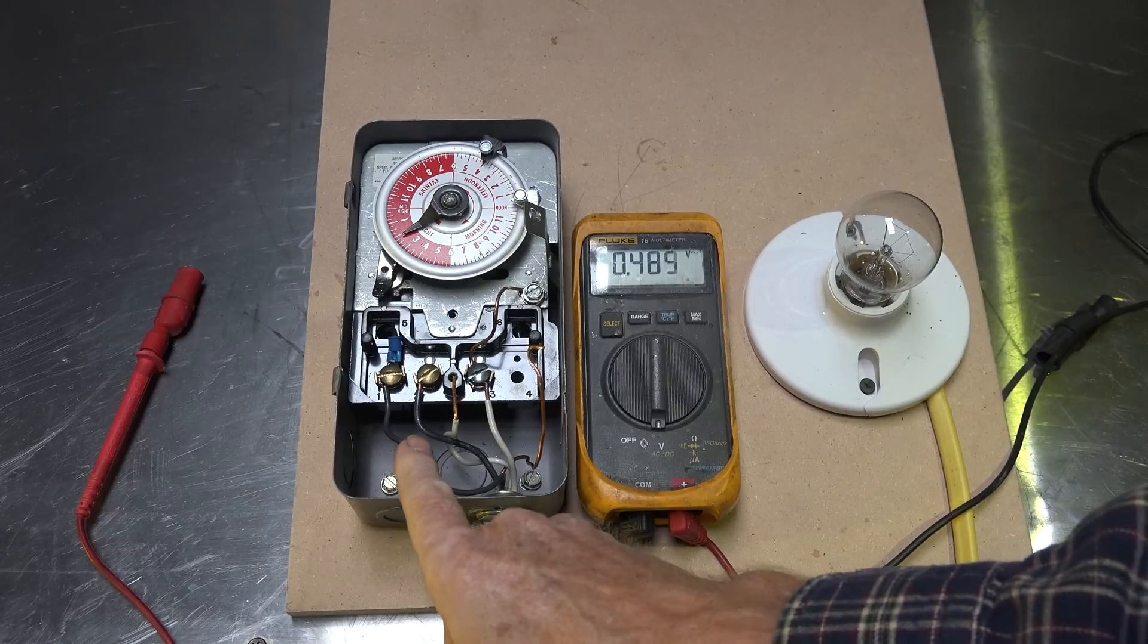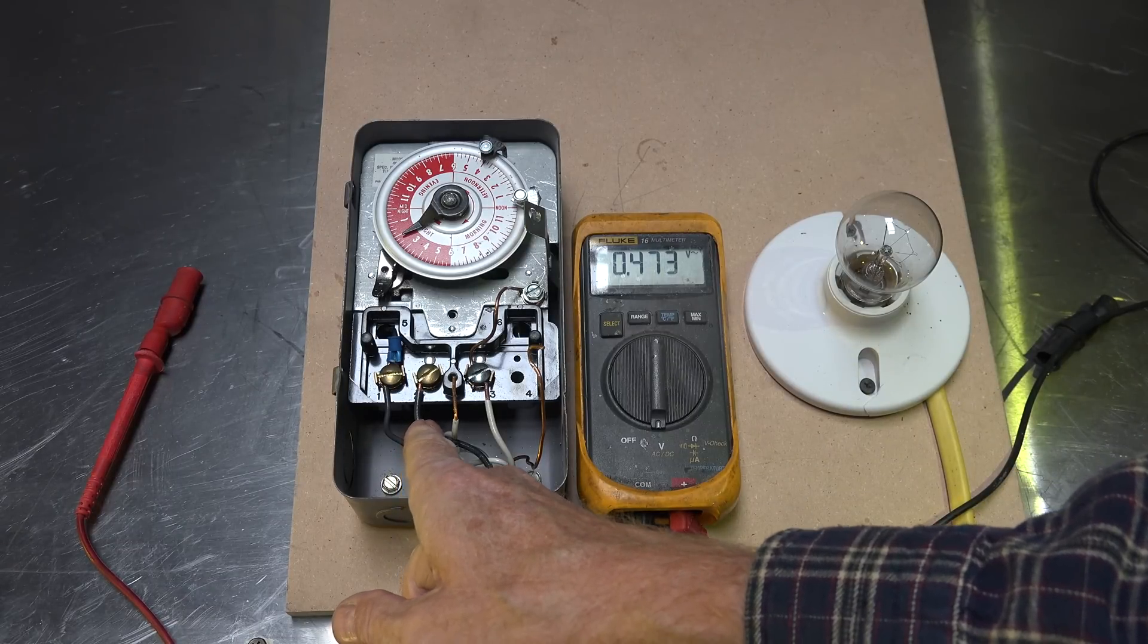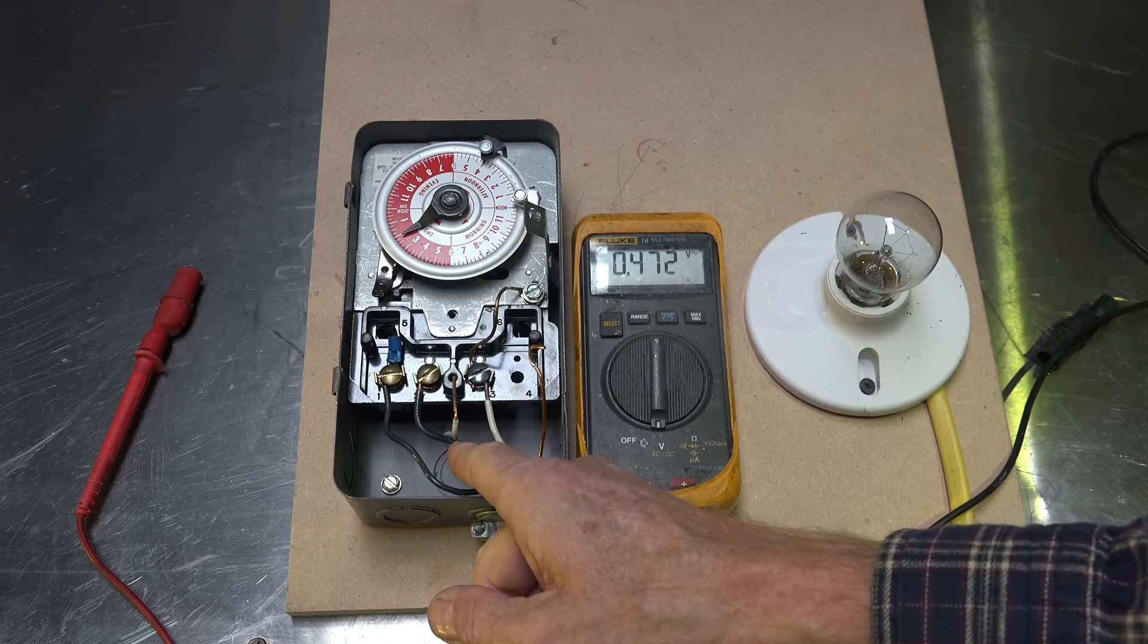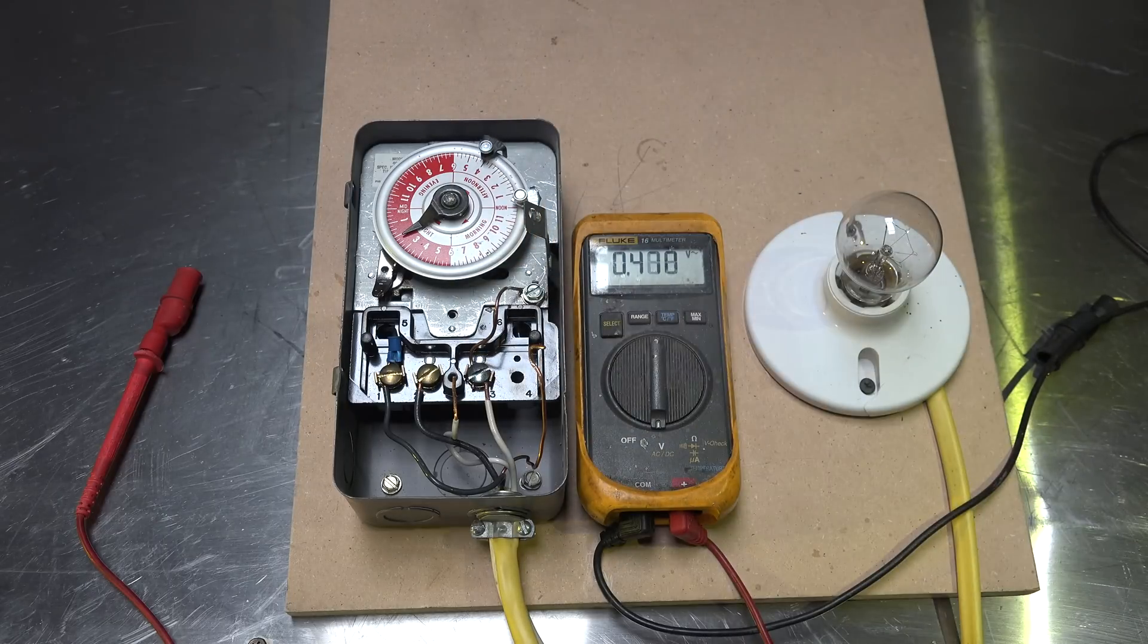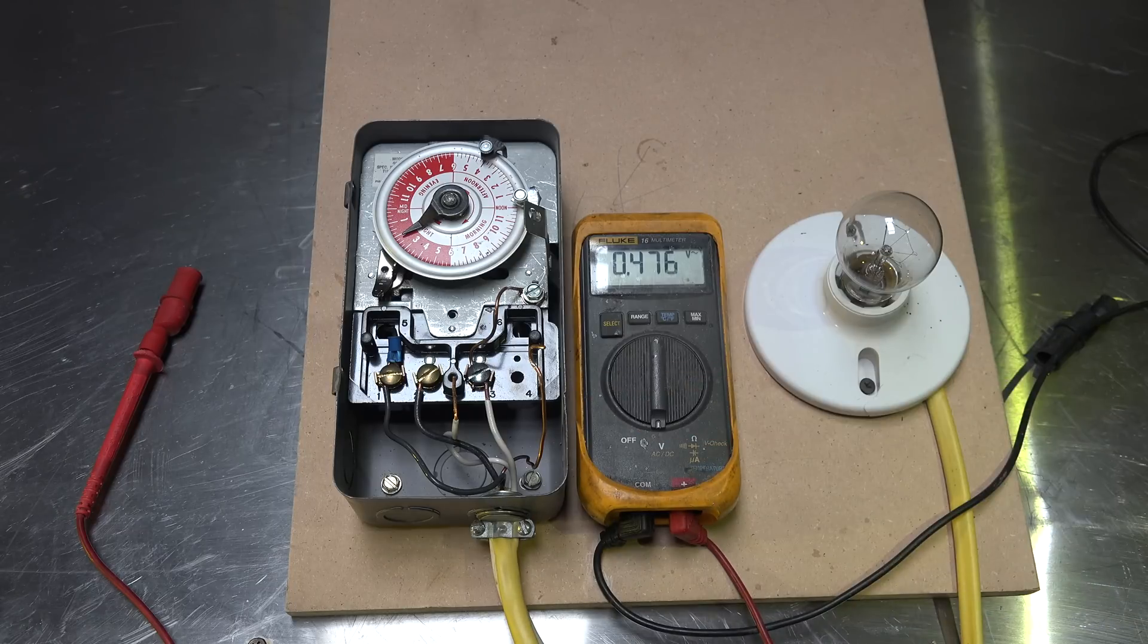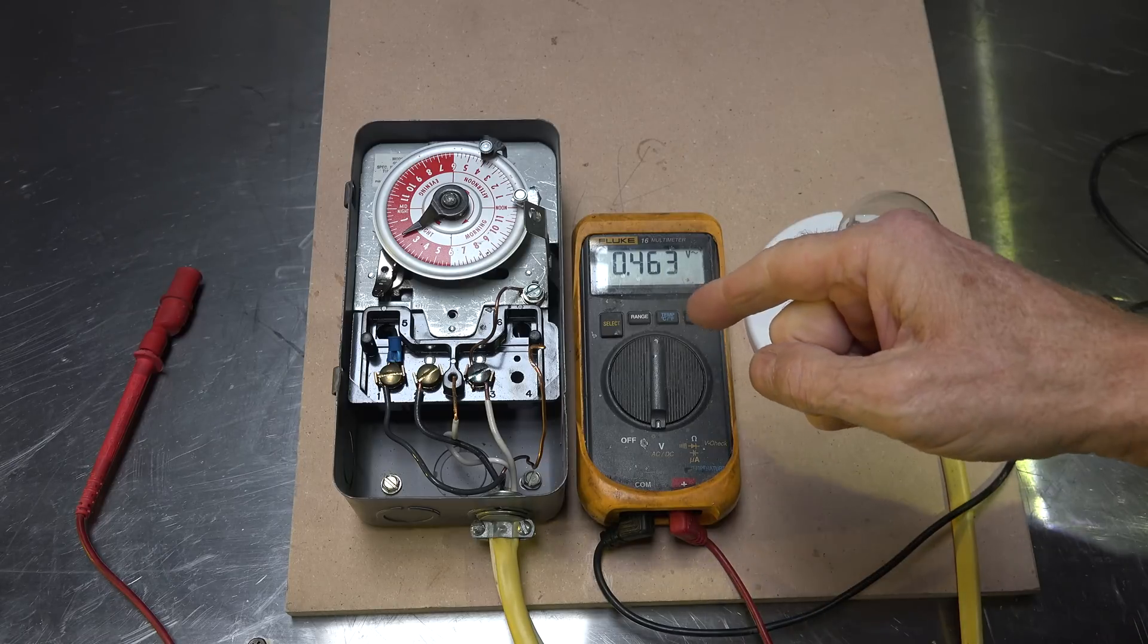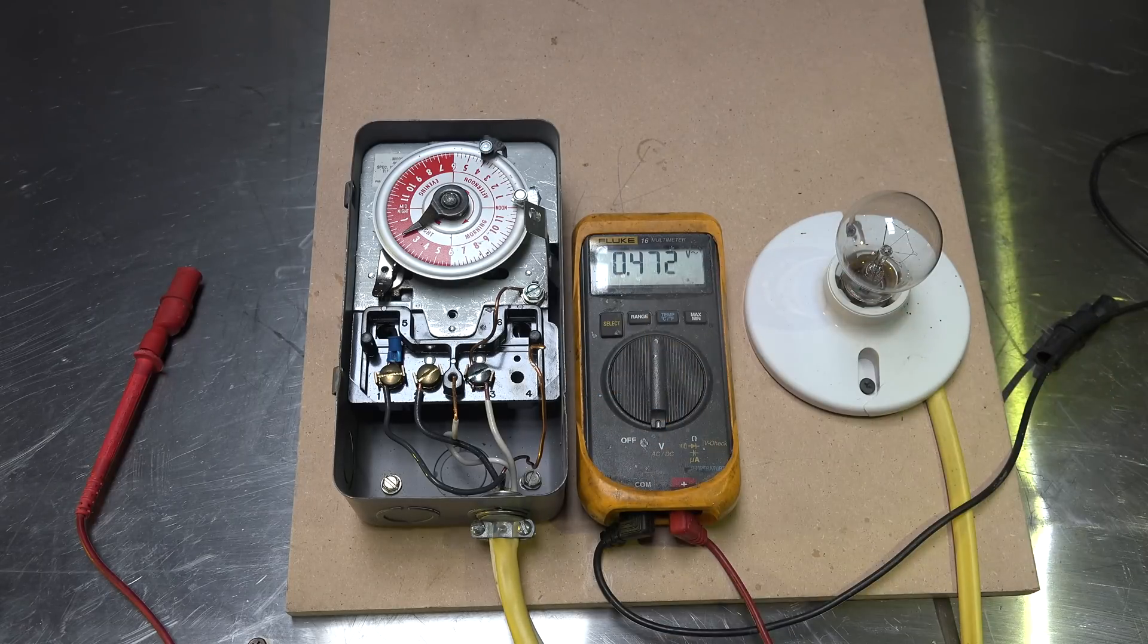So what's happened here—let me pull this terminal off—power is fed through the hot, then it's switched, goes through the light, comes back through the neutral. There's no path back to neutral from the box here. There's a path over here to the chassis of the unit. So once that chassis disconnected that ground—and grounds can be disconnected very easily; oftentimes they're using the conduit for ground—there's not a good path. My box just got hot.